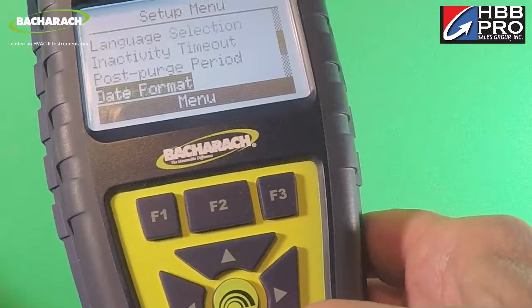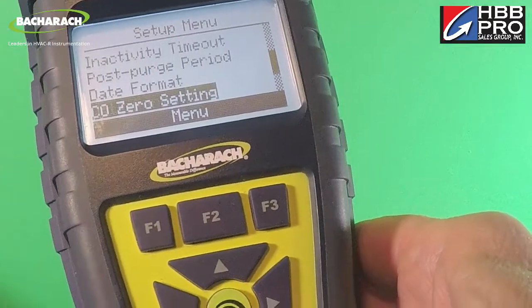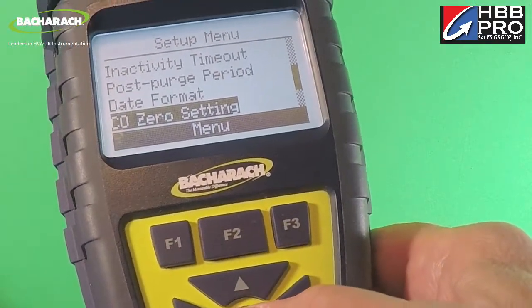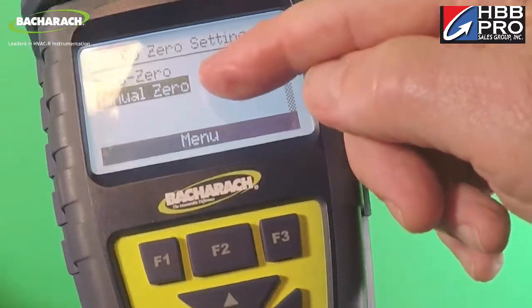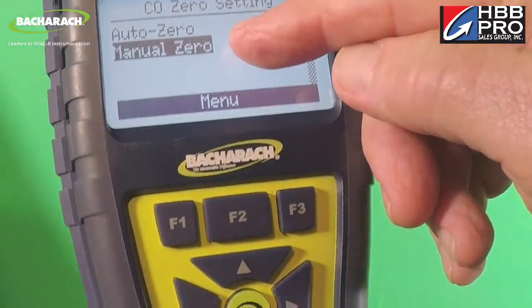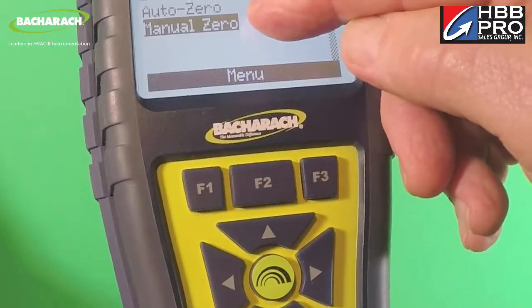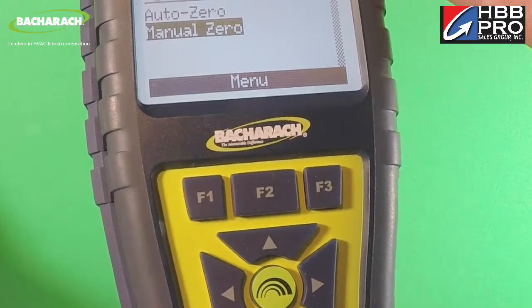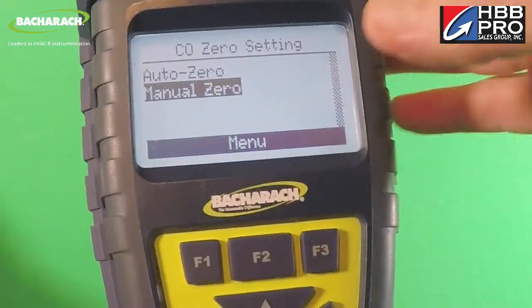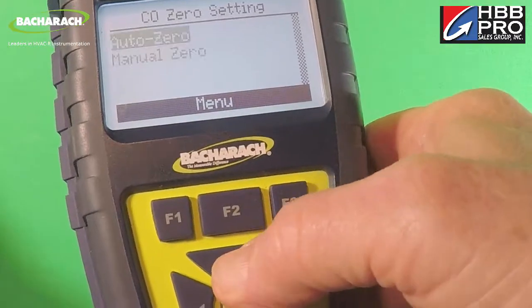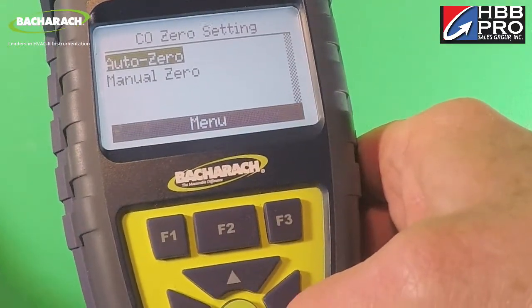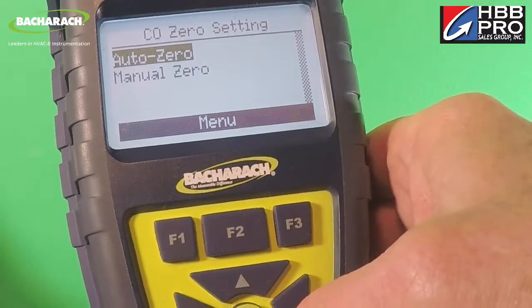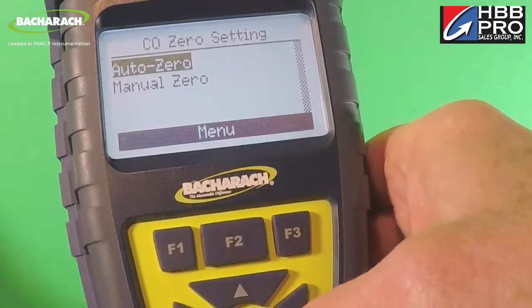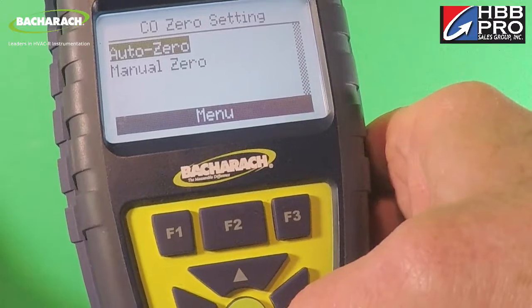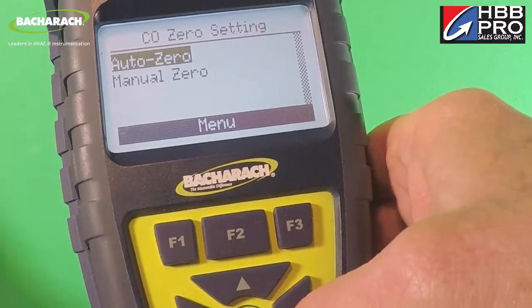Okay, then down to date format, CO 0 setting. This is what I was mentioning earlier. This instrument's set up to do a manual CO 0, or a manual power-up of the sensor is how I say it. What that means is that, let's say there were 5 ppm in the space I was turning the instrument on in, it would come up and say 5 ppm. If I have it set to an auto 0, that's going to try to go to 0 every time, even if there's 5 or 10 ppm in the space. Now, if there's substantial CO levels, you will get an error message in either setting.